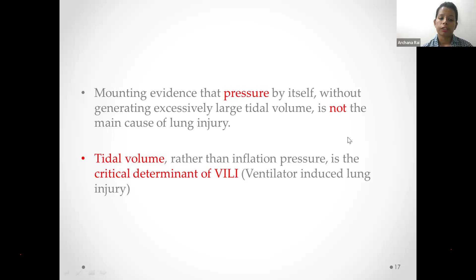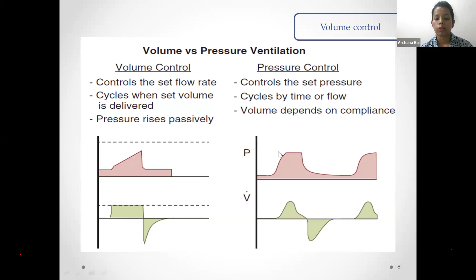Let us see how it is different from the pressure control mode. In the pressure control mode, we set the pressure and it cycles by the time or the flow, and the volume generated will depend upon the compliance of the baby's respiratory system. In volume control, what is set is volume. The set volume will be delivered and the pressure will rise passively. In volume control ventilation, the pressure peaks at the end of inspiration, and in pressure control, it peaks at the start of inspiration.